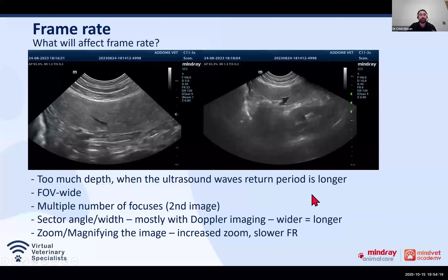So if we have more than one focal point, the frame rate will be slower. So always try, this is the most common thing that I have seen. Also, if we have the field of view really wide, obviously the resolution will also decrease in a way and the image will be slower. So I will say that those are the most common things that I'm seeing when we have an image in slow motion. It doesn't mean that the machine is broken. It means that it's taking a bit longer to process all the information. Okay.